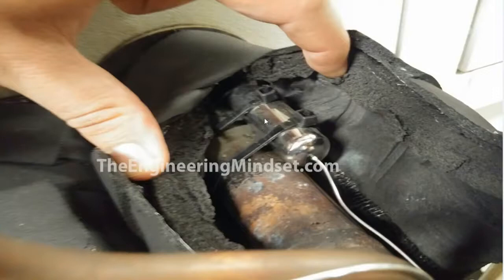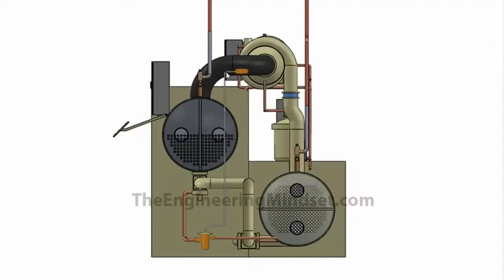As that expands, it pushes refrigerant out through the capillary tube, and that causes a pressure increase in the capillary tube, and that pressure pushes all the way along the capillary tube, all the way down through it and into the top of the pilot valve. So that pressure is pushing down onto the top of the valve, and with that you can now control the valve depending on the level of superheat.